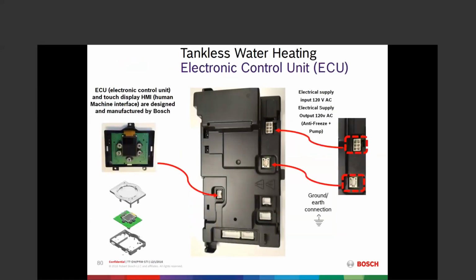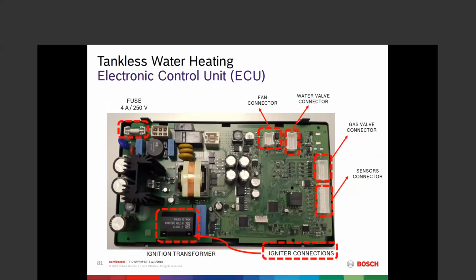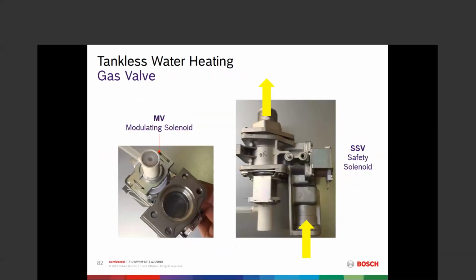And as you can see, it's all plugs on that control on the ECU. It's all plugs. The only serviceable component, and hopefully that saves us from any surges, is this 4 amp fuse inside of the box. Aside from that, there's nothing that's serviceable on this printed circuitry. Modulating gas valve. So at the bottom, we actually have two gas valves. We have our safety solenoid, which shuts off all gas flow to the unit. Then we have our modulating solenoid that allows for the variable input.